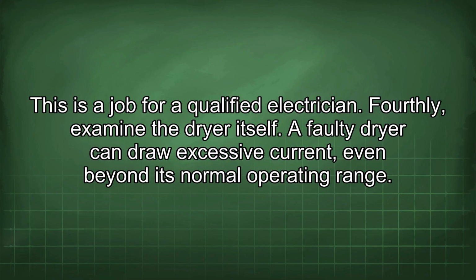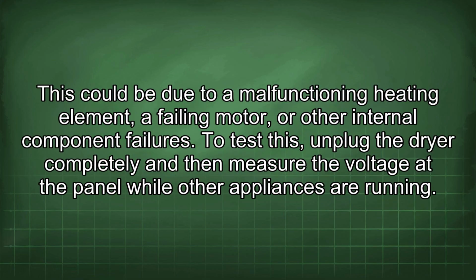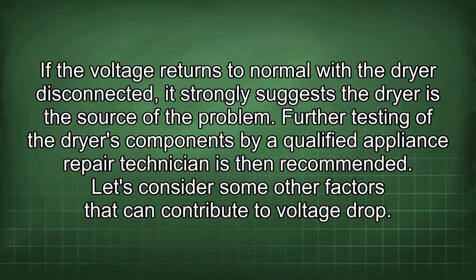Fourthly, examine the dryer itself. A faulty dryer can draw excessive current even beyond its normal operating range. This could be due to a malfunctioning heating element, a failing motor, or other internal component failures. To test this, unplug the dryer completely and then measure the voltage at the panel while other appliances are running. If the voltage returns to normal with the dryer disconnected, it strongly suggests the dryer is the source of the problem. Further testing of the dryer's components by a qualified appliance repair technician is then recommended.